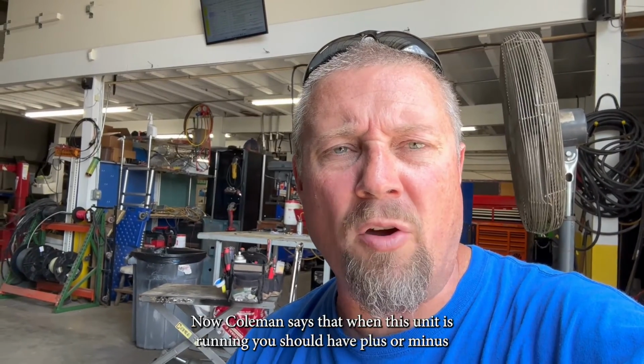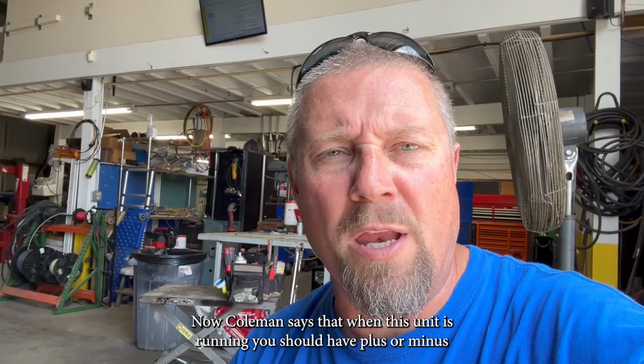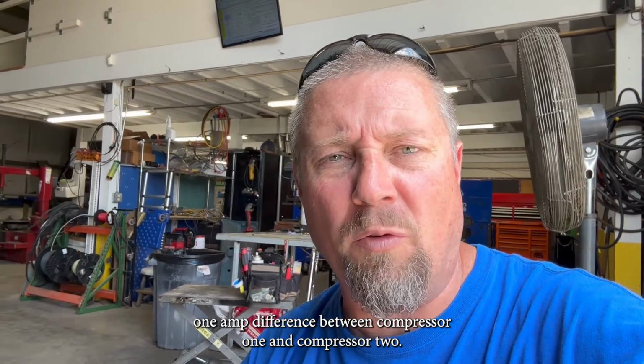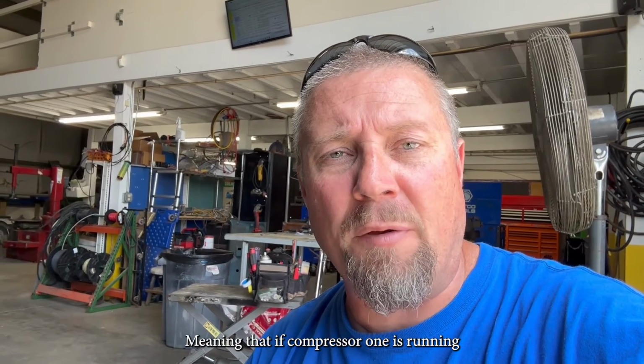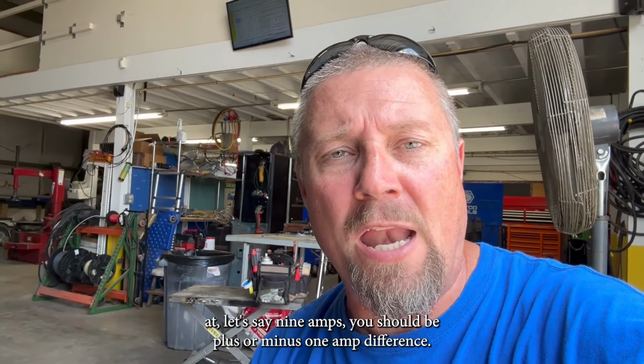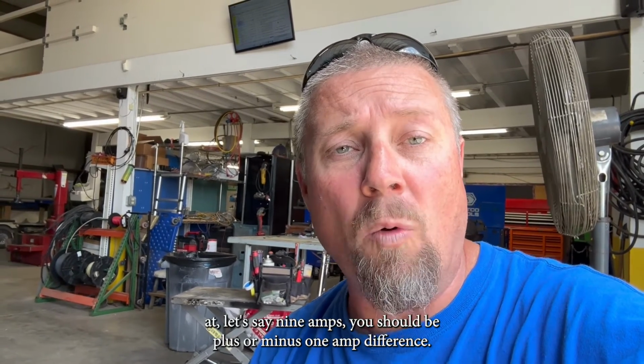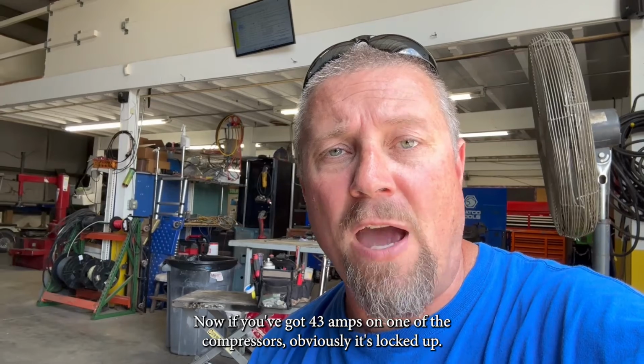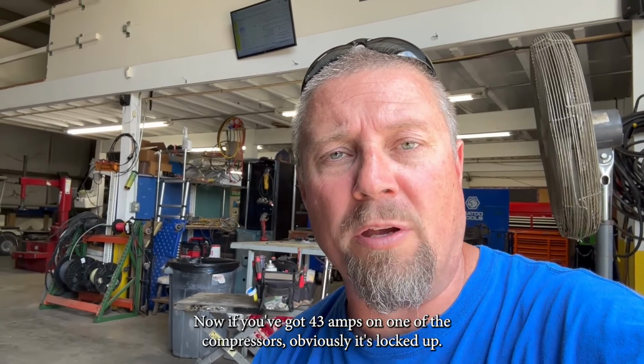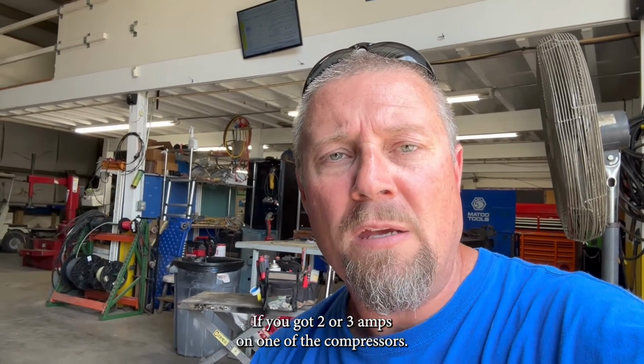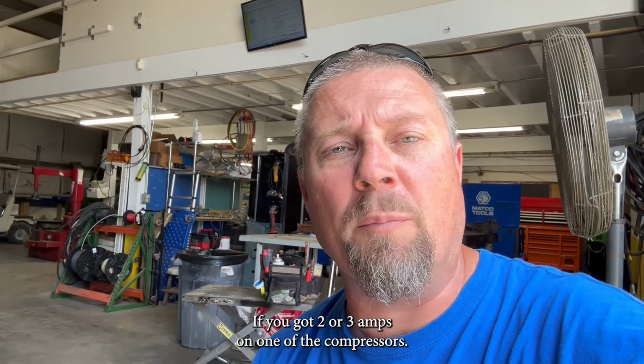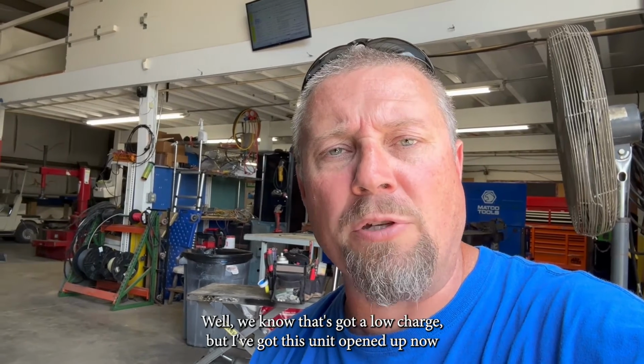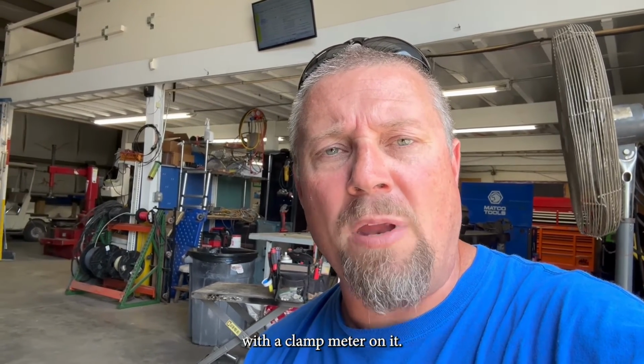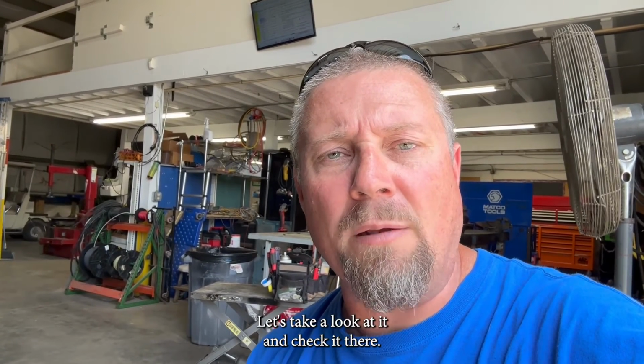We've got it running. Now, Coleman says that when this unit is running, you should have plus or minus 1 amp difference between compressor 1 and compressor 2. Meaning that if compressor 1 is running at, let's say, 9 amps, you should be plus or minus 1 amp difference. Now, if you've got 43 amps on one of the compressors, obviously it's locked up. If you've got 2 or 3 amps on one of the compressors, we know that it's got a low charge. But I've got this unit opened up now with a clamp-on meter on it. Let's take a look at it and check it now.